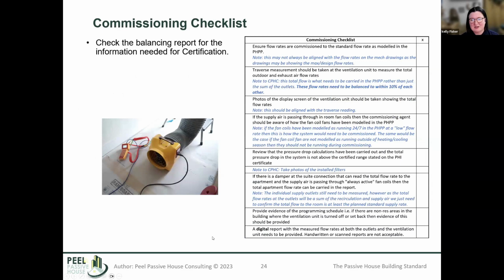This is just a commissioning checklist that we typically use when we receive commissioning reports as certifiers, things that we go through to make sure that everything is done properly and in line with what we have to submit to the Passive House Institute for certification. There's a lot of little nuances that are required with respect to balancing and the commissioning reports. And I just included this as a good reference because there might be people out there who would want a preliminary checklist to go through as you're getting into your larger projects or your multifamily.